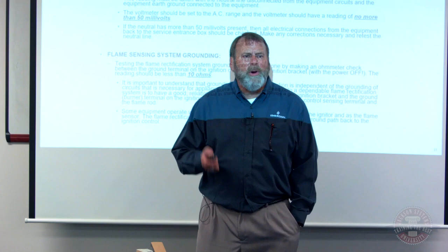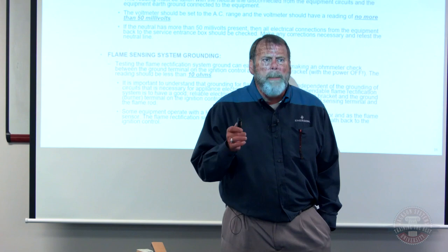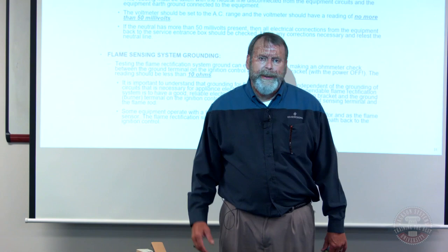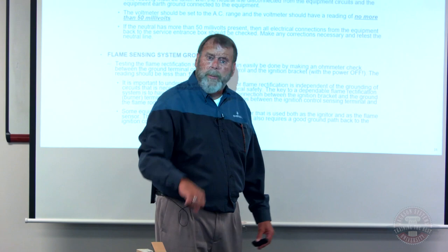And what was crazy was our tech service AC and ref side of the business, we had an abnormal amount of phone calls coming in. And we finally figured out what the problem was because it was all dealing with ground. And I thought, why are we having these ground issues? How do they ground a house? They take a big long stake, they pound it into the ground, hook a big honking wire up it, and pull it into the breaker box.